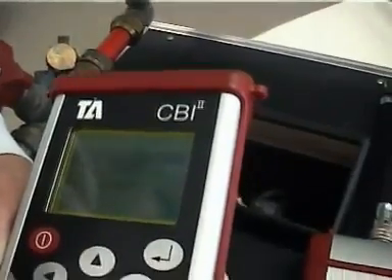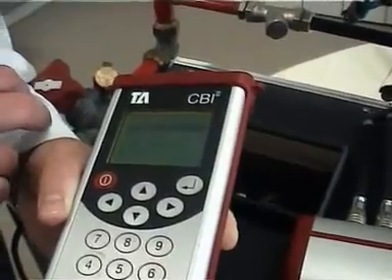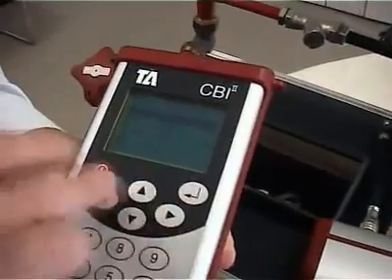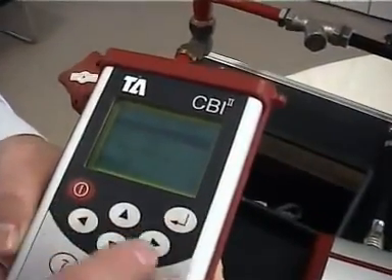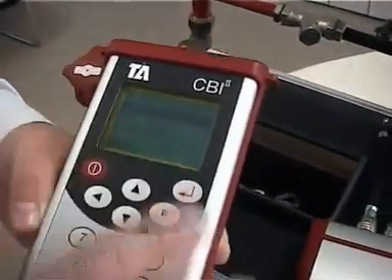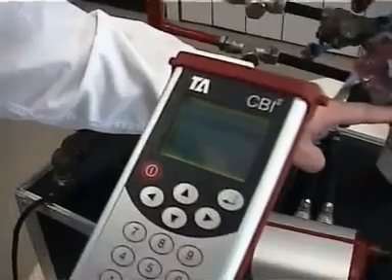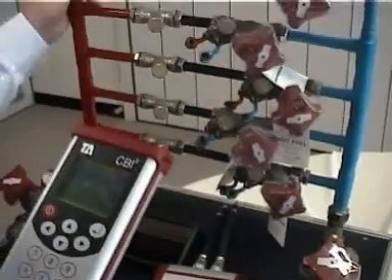With this type of balance, you only need to visit the valves a maximum of three times. By scrolling through the systems and changing the valve numbers up the top from the systems, from one to five, we've gone around and preset all our valves to the required position settings. The system now is balanced to plus or minus 10% with the available water flow going through the system.